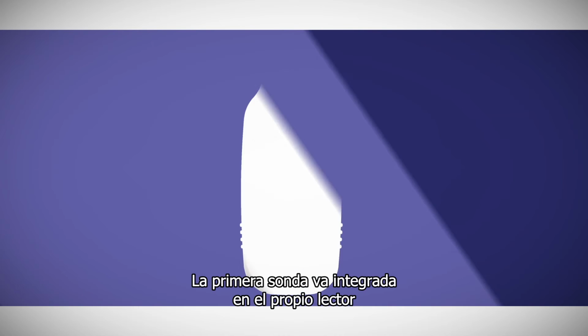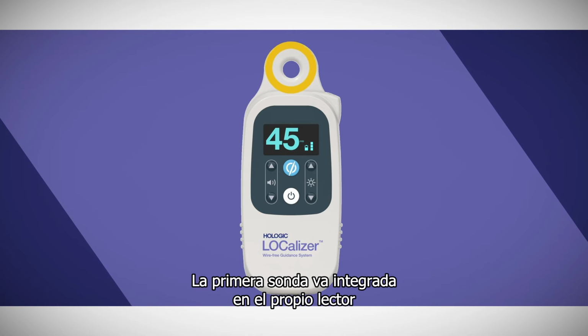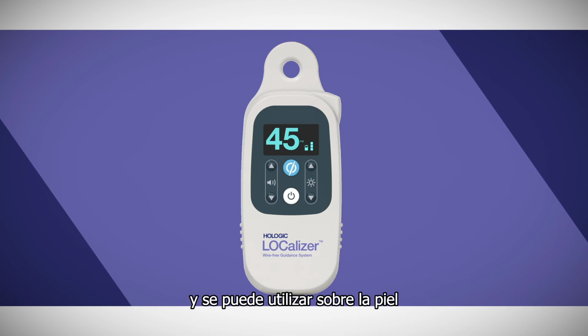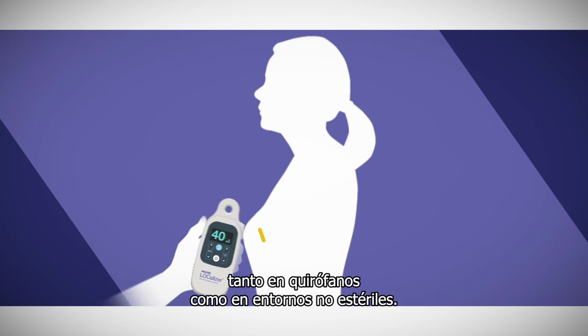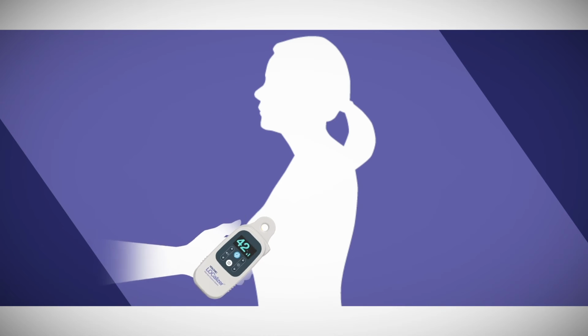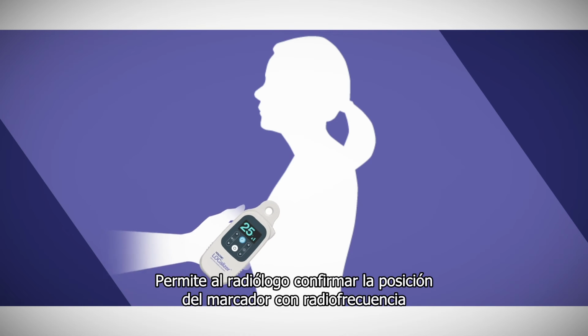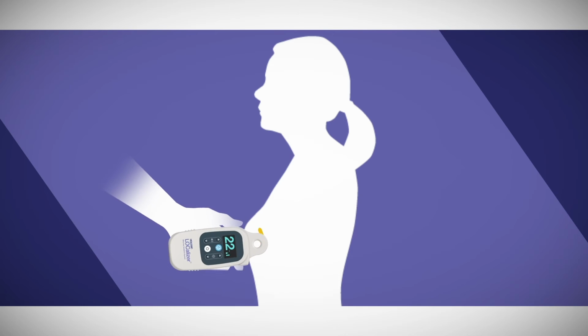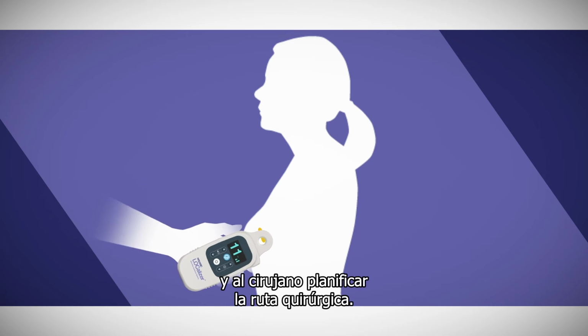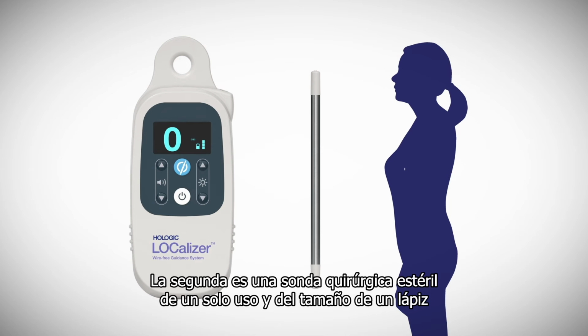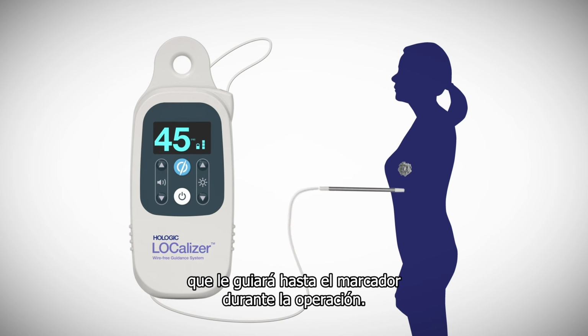The LOCalizer has 2 detection probes. The first probe is integrated into the reader itself and can be used on the skin's surface in both the sterile surgical field and non-sterile environments. This probe can be used by the radiologist to confirm the position of the tag and by the surgeon to plan the surgical path. The second is a pencil-sized, single-use sterile surgical probe that guides you towards the tag during the operation.